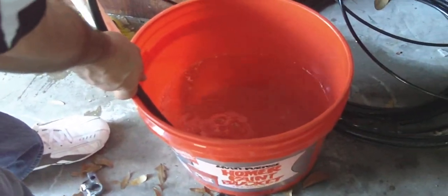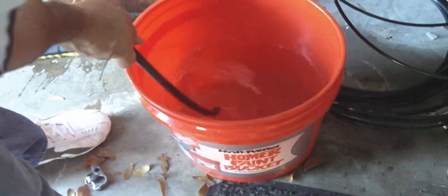Now if you're continually getting air bubbles in there, then you know you have an issue with air somewhere on the inlet side of your system. Another thing that's good about the bucket trick is if you suspect that when doing two GPM systems or multiple systems, you want to check your flow rate with a bucket.